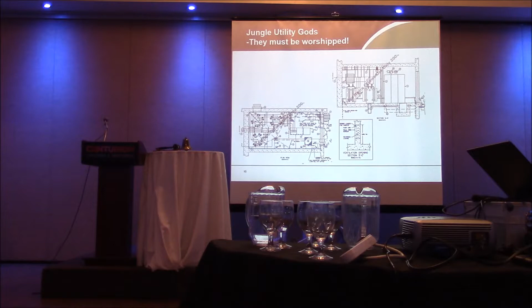Air conditioning - yeah, we're going to spend a bunch of energy on air conditioning to cool the room. I'm seeing this more and more, electrical rooms that are air conditioned. There are two reasons: one, believe it or not, there are unions that don't want electricians working in environments that are too warm. Apparently an electrical room at 75 or 80 degrees Fahrenheit is considered too warm, and the guys won't work in there. So they're air conditioning electrical rooms. But think about it, we've got to spend energy to get the heat out of the room, so I'm increasing my transformer size.